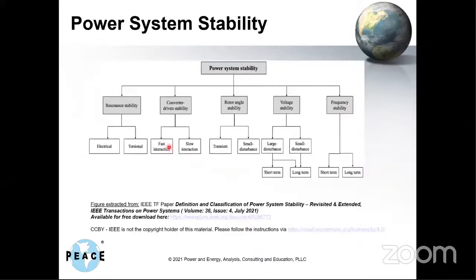And we may also have resonant stability. So those very fast controls may interact with other devices on the grid, like, let's say, if there's an HVDC nearby, or if there's a series capacitor, we might get a resonance between the asynchronous machine's magnetizing reactance, the series cap, and the converter controls may introduce even more negative damping. So we have to look at those kinds of phenomena.